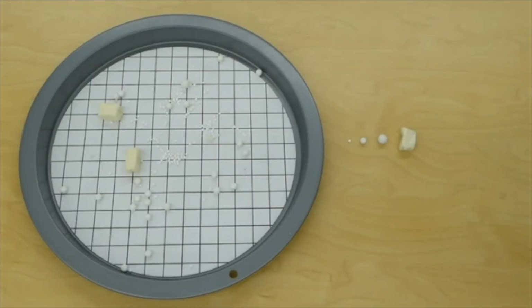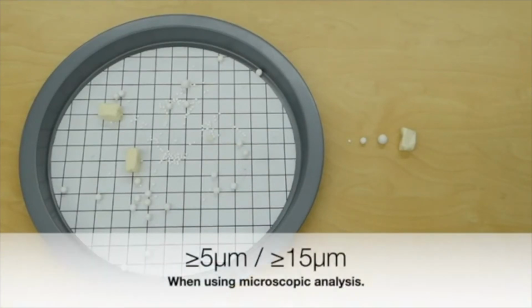All right. Now, there's two ways of looking at this. The first way is with microscopic analysis. Microscopic analysis uses the size designations of 5 micron and greater and 15 micron and greater. So for the purposes of the exercise, I will say that that is a 5 micron particle, or say 6 is greater than 5. And we'll say that that's about an 18 or 20 micron particle. So that's going to be the sizes.